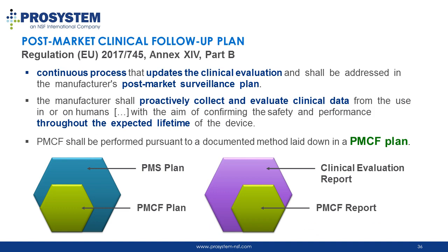The post-market surveillance plan should also address post-market clinical follow-up activities. Post-market clinical follow-up activities, or PMCF, is a continuous process to proactively collect and evaluate clinical data throughout the expected lifetime of the device, such as the performance of literature search or user surveys.